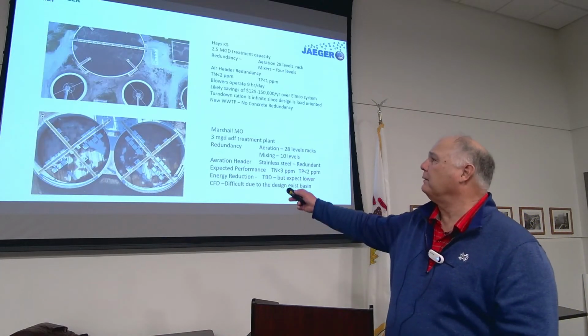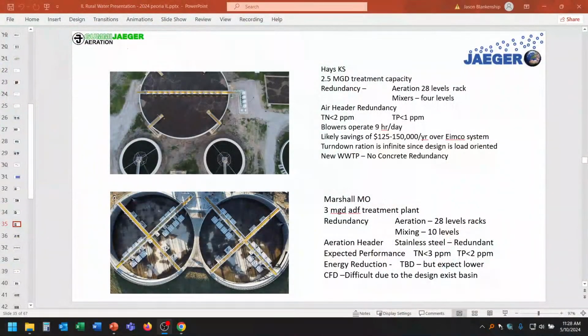But this plant, we went back and gave them a total nitrogen discharge in a few weeks. This plant at the top is Hays, Kansas. Blowers only run about 7-8 hours a day. Again, we have 28 levels of aeration redundancy out there. We could pick any one of these up and move it away.